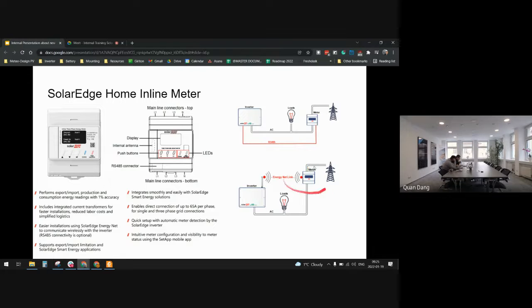Right now, this works something similar to — I think Fronius, for example, also has an inline meter. You connect the incoming line from the grid directly to the meter and then it goes out, connecting directly on the line without a current transformer. The current rating goes up to 65 amps, so I think almost all residential houses will fit this criteria, because 63 amps is already a pretty big house.